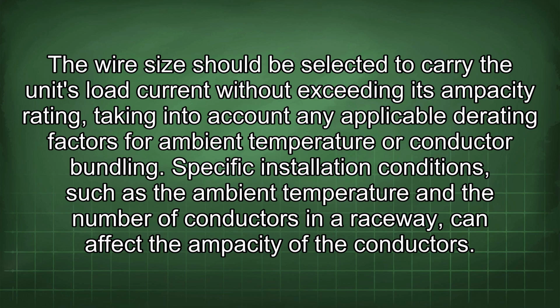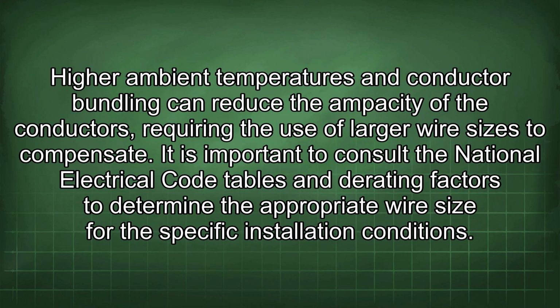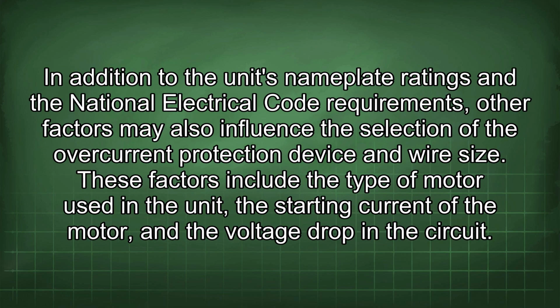Specific installation conditions, such as the ambient temperature and the number of conductors in a raceway, can affect the ampacity of the conductors. Higher ambient temperatures and conductor bundling can reduce the ampacity of the conductors, requiring the use of larger wire sizes to compensate. It is important to consult the National Electrical Code tables and derating factors to determine the appropriate wire size for the specific installation conditions. In addition to the unit's nameplate ratings and the National Electrical Code requirements, other factors may also influence the selection of the overcurrent protection device and wire size.